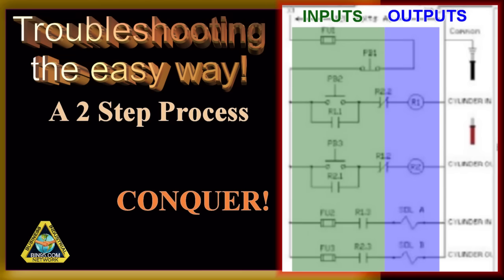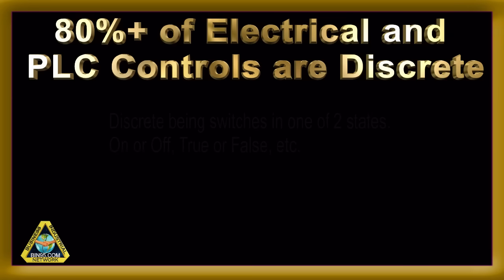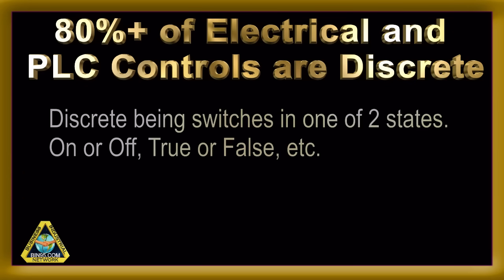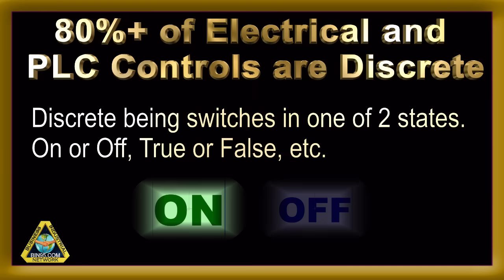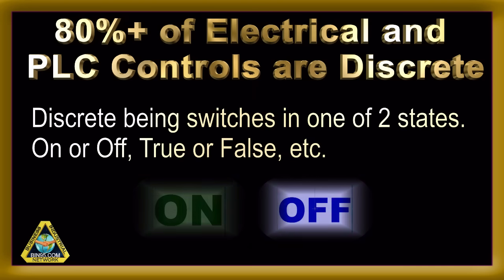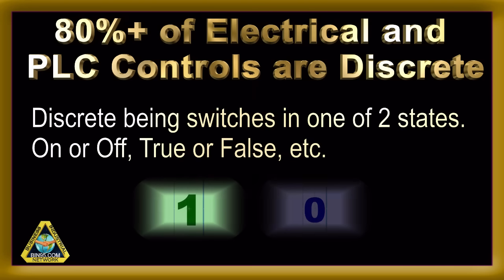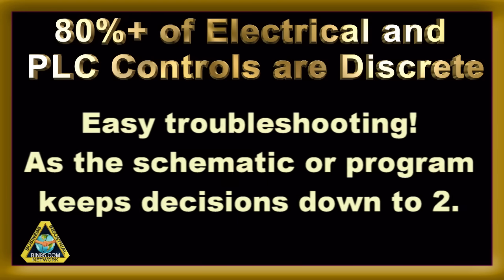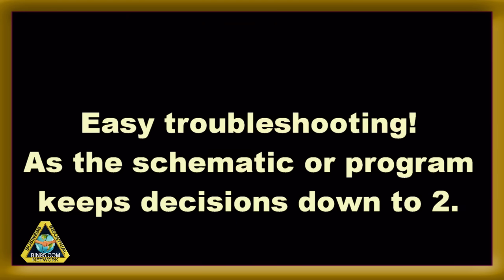Your first divide is to decide to start the circuit trace with the input or output. 80% or more of electrical and PLC controls are discrete. Discrete means a switch in one of two states: on or off, one or zero, true or false. Easy troubleshooting because the schematic or program keeps decisions down to two.